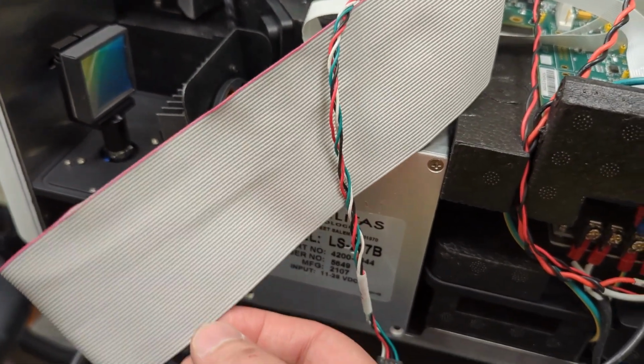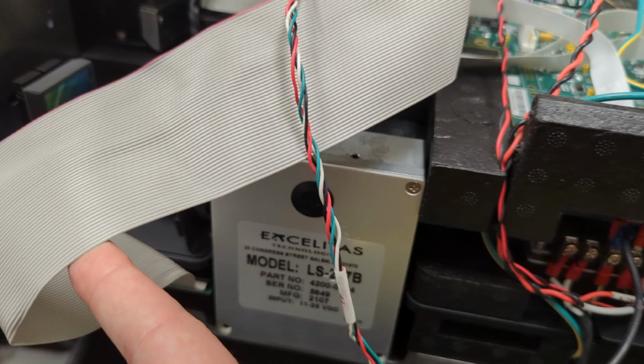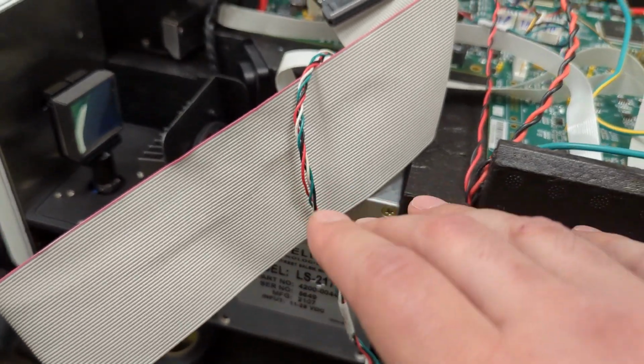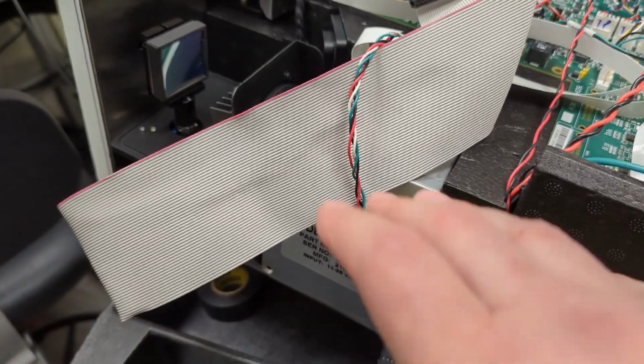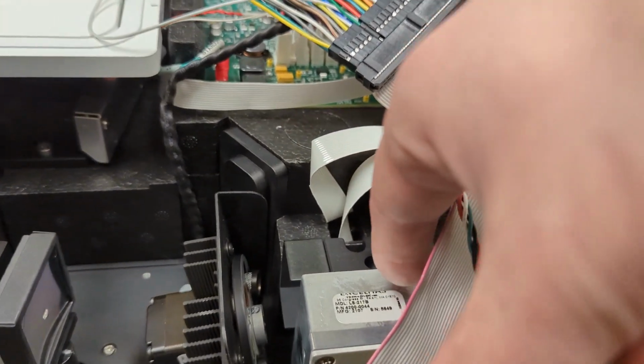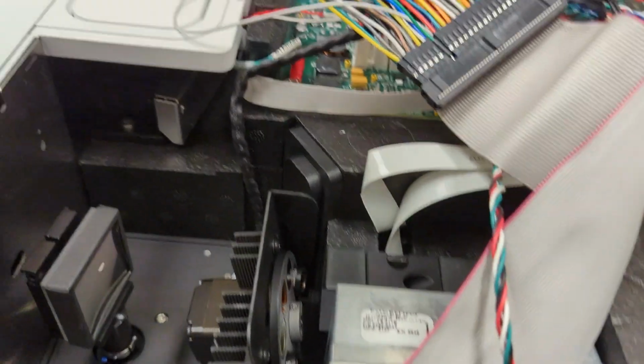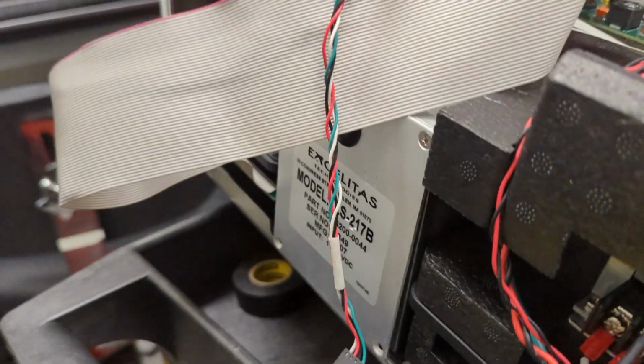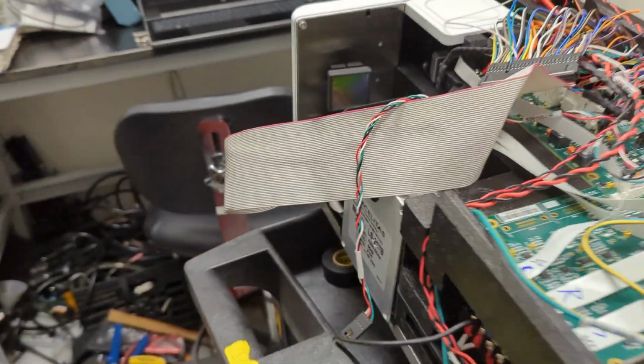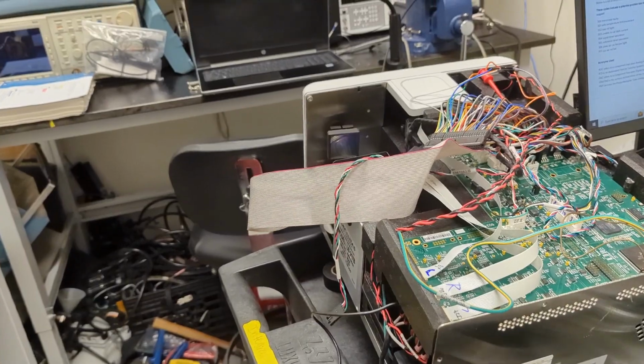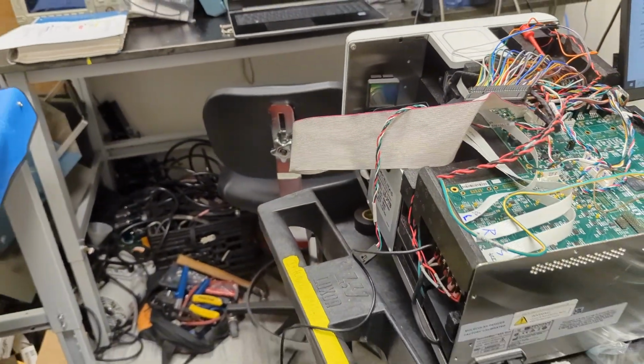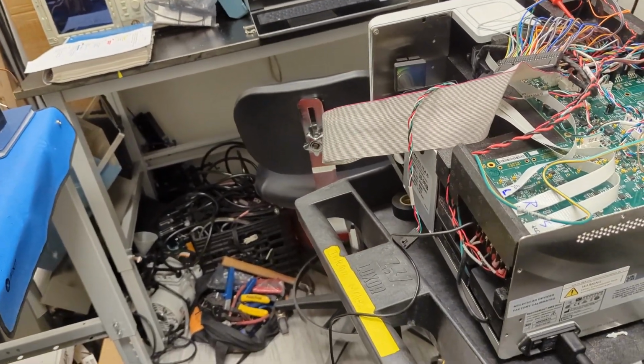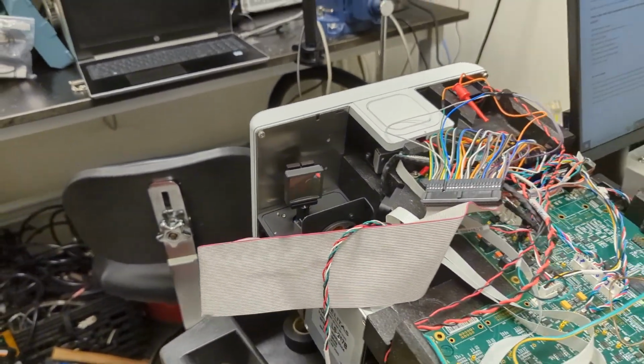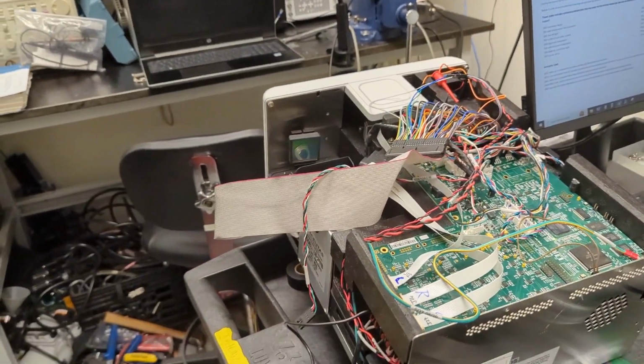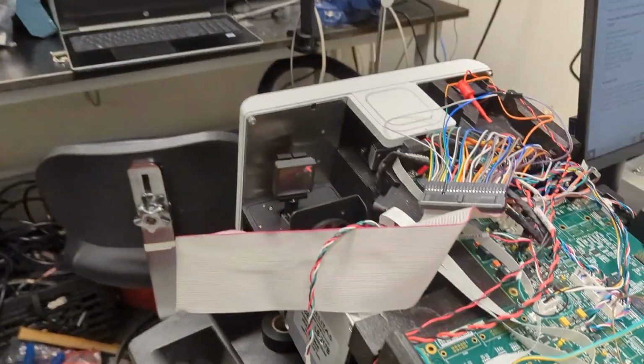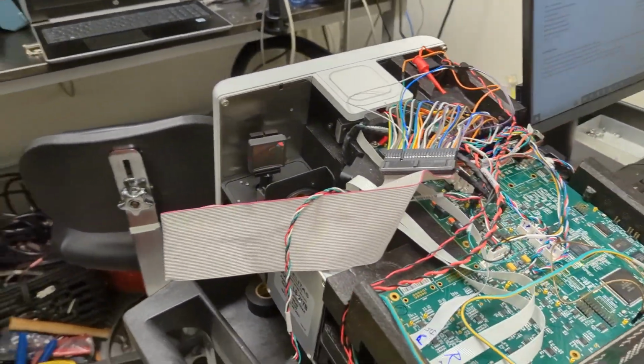Starting with the light source. So lifting up this ribbon cable here, this is the light source. It is a module that has the lamp, which is a xenon flash lamp, and that's basically sitting right around here, and then there's a mirror that directs the light this way. It's attached to the high voltage power supply for that lamp. Now, xenon flash lamps require a much higher voltage than mains, and it's DC. They usually operate at anywhere from 300 to 1,000 volts DC, and that voltage is usually pulsed at different frequencies, depending on the application. This unit can change that pulse depending on what's needed.